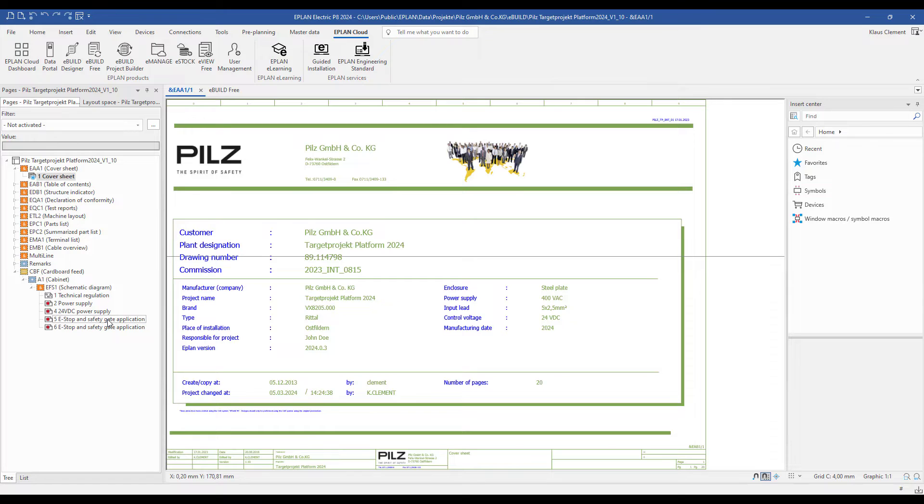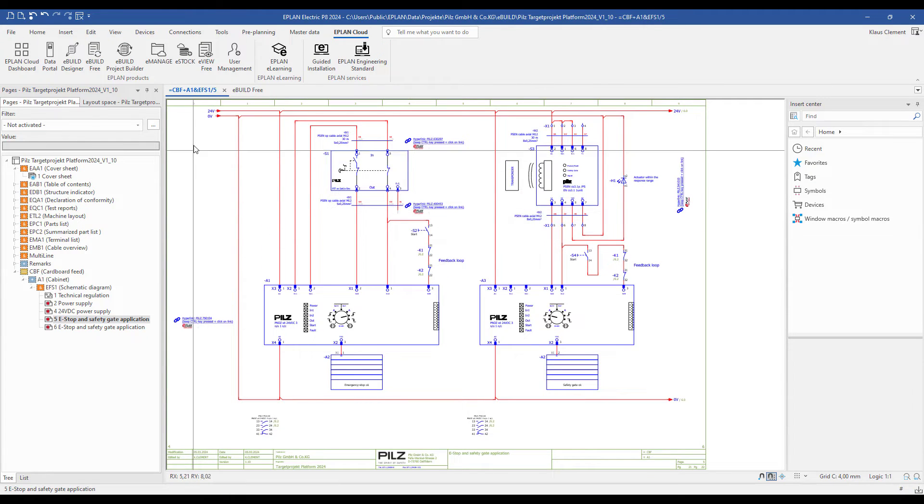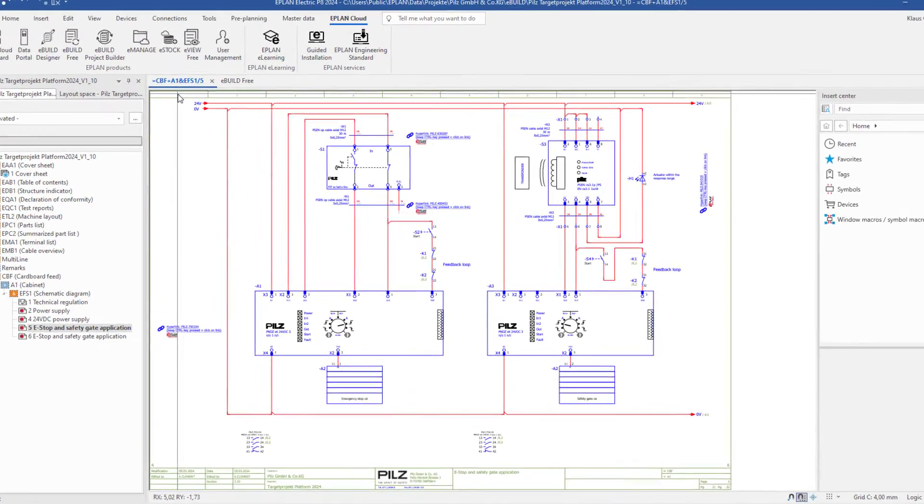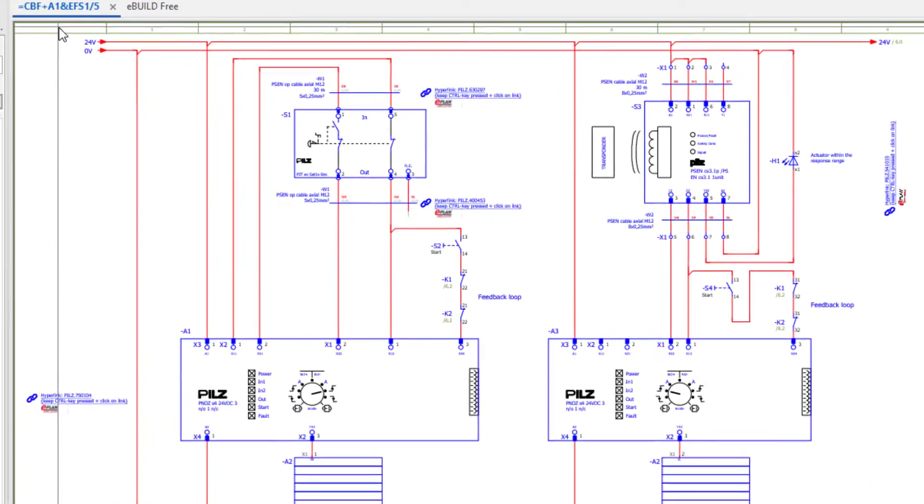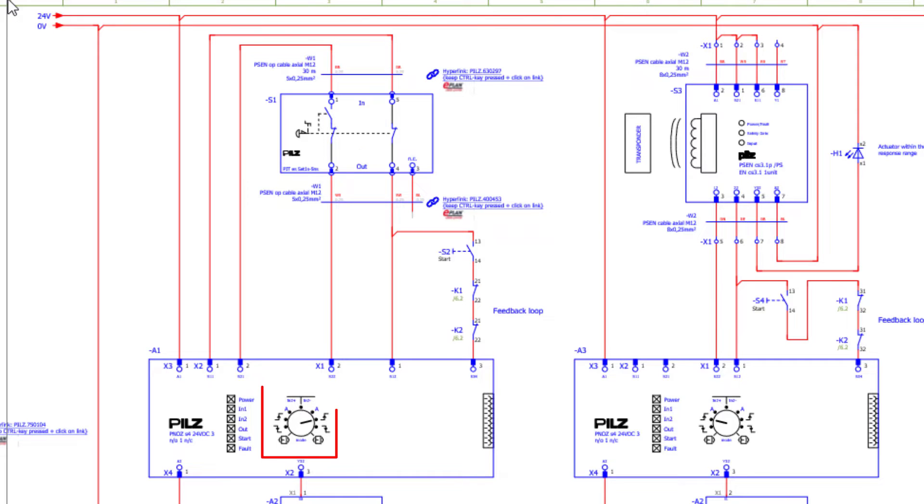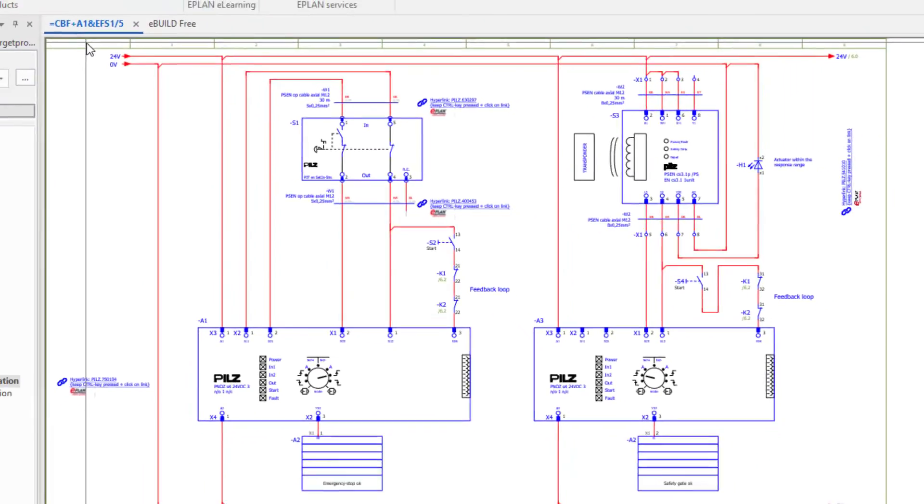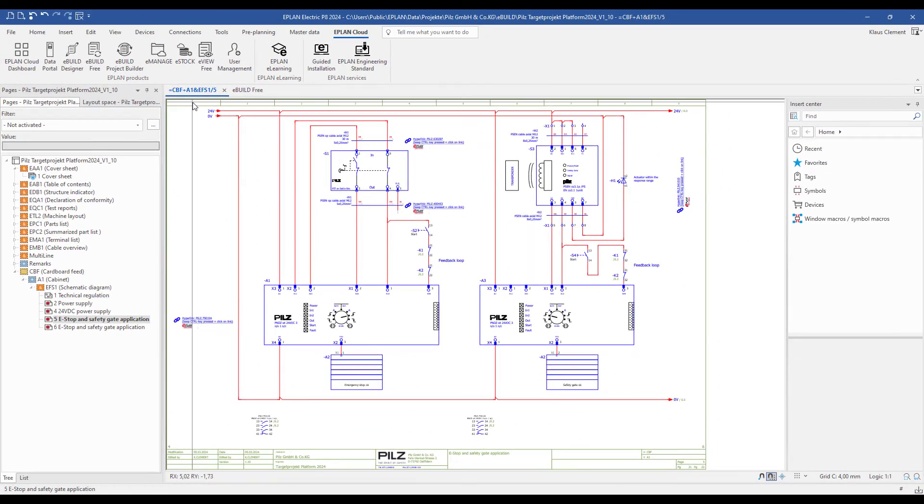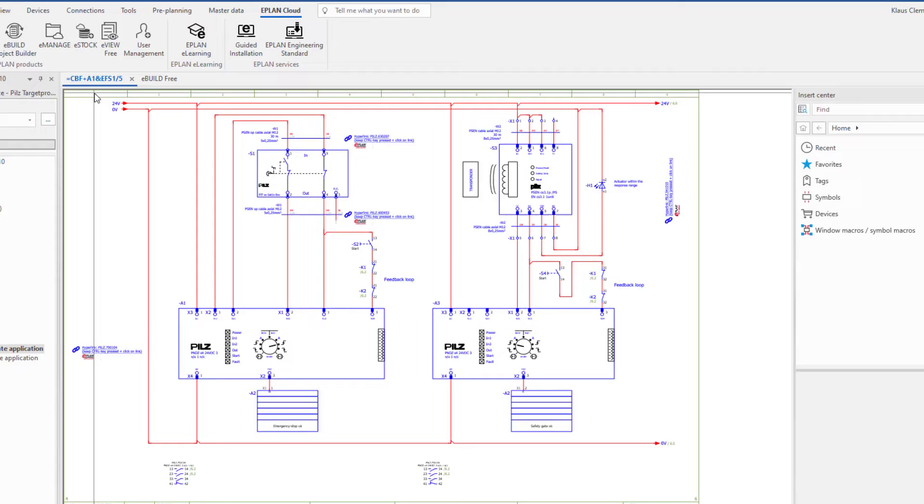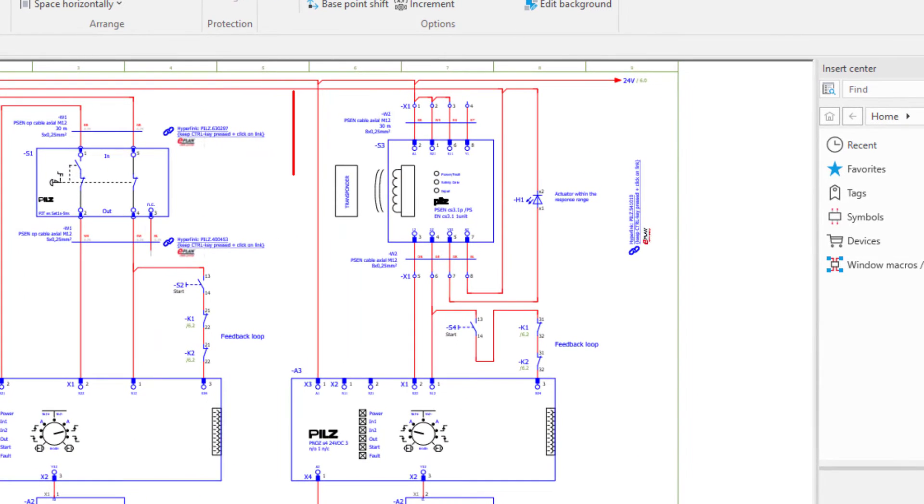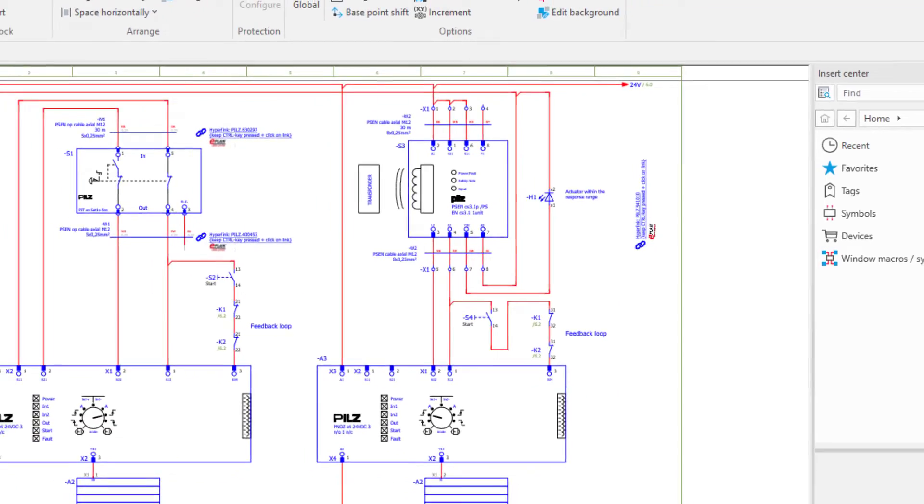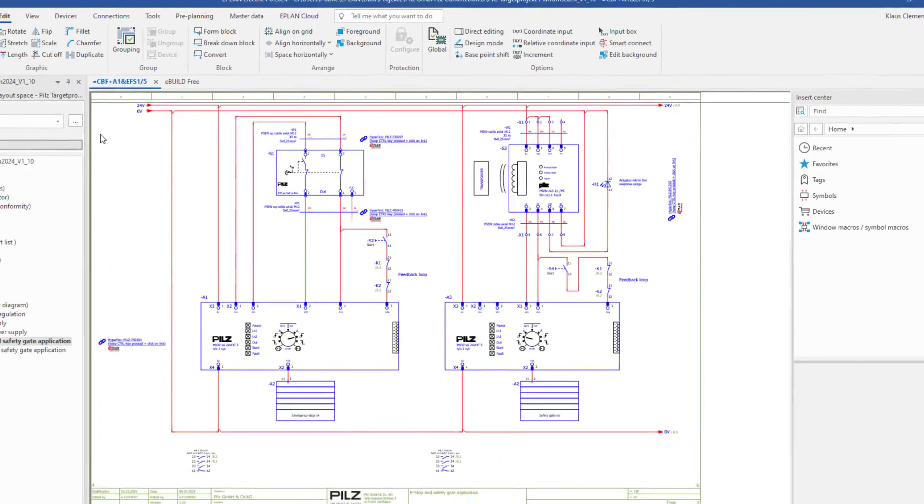I open my target project page number 5 with my safety application. You can see on the left side a dual channel E-Stop button with detection of short across contacts, feedback loop monitoring and manual start. On the right side you can see a dual channel safety gate sensor with monitored start and feedback loop monitoring.